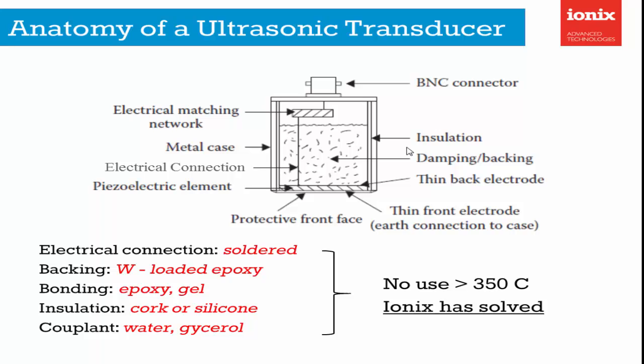This backing material, which fills this space, is conventionally tungsten loaded epoxy. Its properties are that it must have the same acoustic impedance as the piezo, so the energy going backwards goes into it but then scatters - essentially a composite matching the impedance product of the piezo.